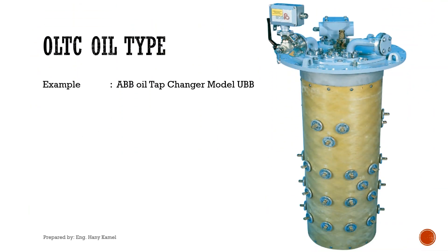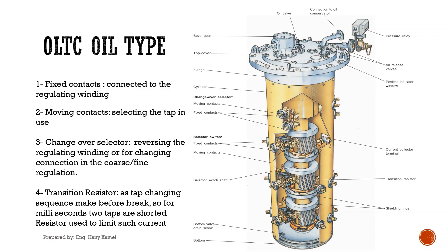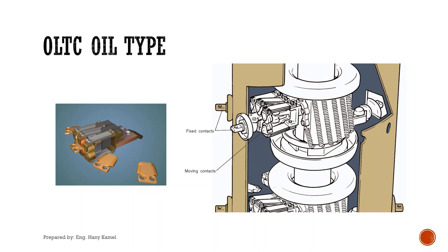On-load tap changer — I will start with OLTC oil type. I will select ABB oil tap changer model UBB as an example. The on-load tap changer main parts: fixed contacts, which are connected to the taps of the regulating winding; moving contacts, which will select the desired tap of the fixed contacts; changeover selector, used in regulating winding reversing application and in coarse-fine application — I will talk in detail about these applications in another video. Transition resistor: as the tap changing sequence is make-before-break, for a few milliseconds two taps are shorted to maintain the load, and the resistor is used to limit the short circuit current in the two shorted taps. In these pictures we can see the fixed contacts and the moving contacts.